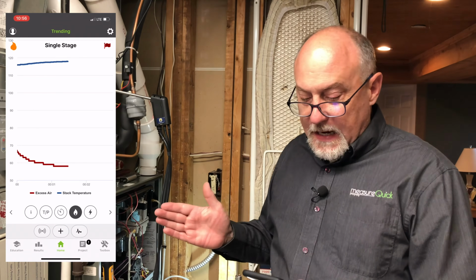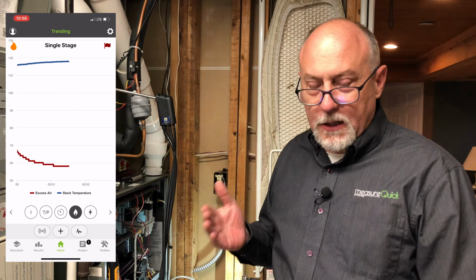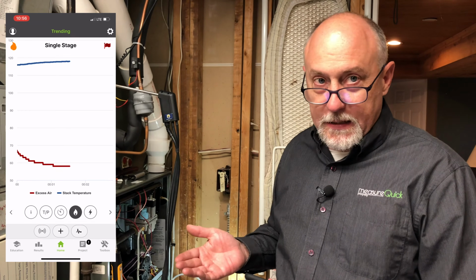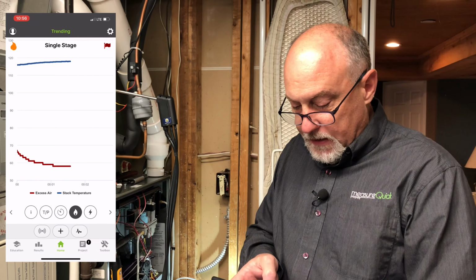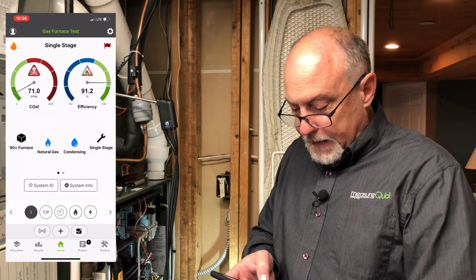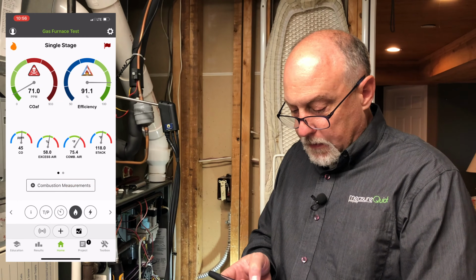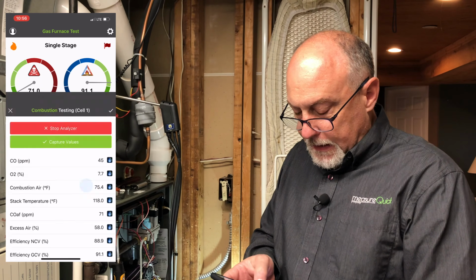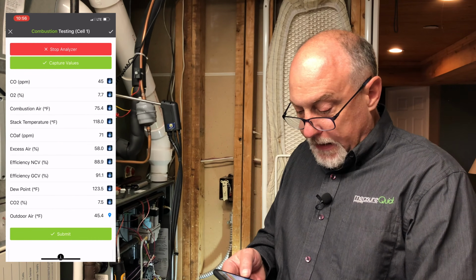All right, so you can see our stack temperature has stabilized and our excess air reading is stable, which is a pretty good indication that the appliance is ready for combustion testing. So I'm going to go back into the flame and combustion measurements, and then I can look at all my readings coming in here.